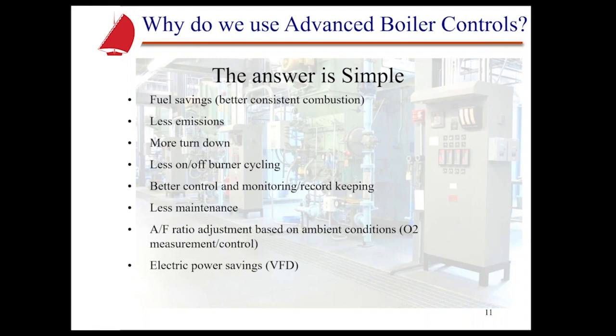So we've got better control. Also with these controls, we get better monitoring and better record keeping because we can actually monitor a lot more measurements, a lot more data. So that's a huge advantage also for record keeping. Also, there's less maintenance. If we're operating that burner at the most efficient point all the time, we're going to have less sooting in the boiler itself. So we're going to have less maintenance required. Again, keeping our efficiency good over a long length of time.